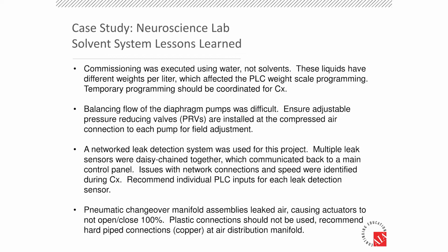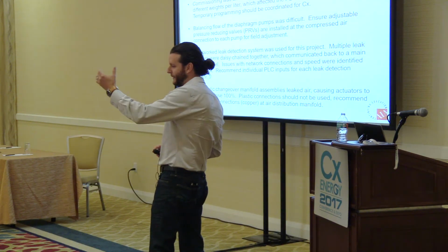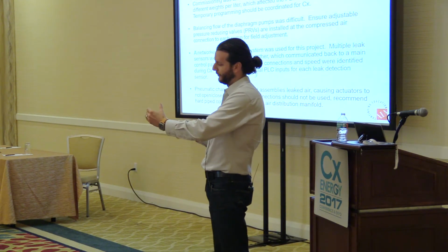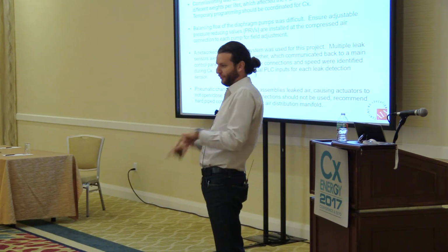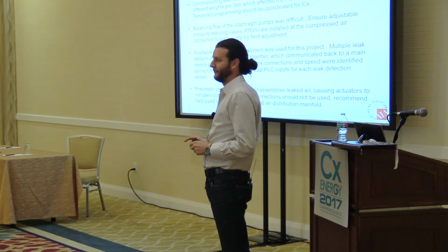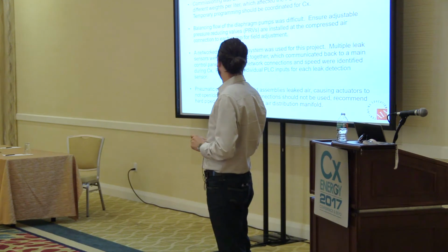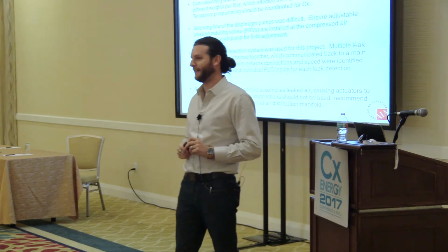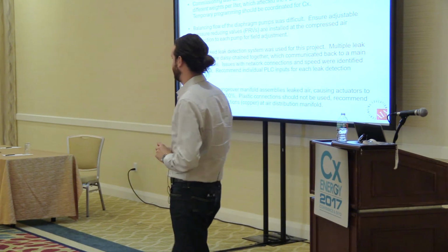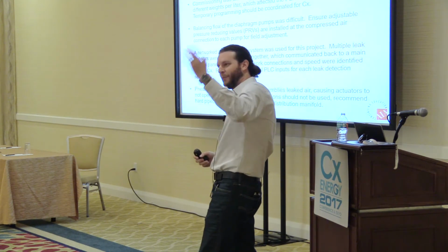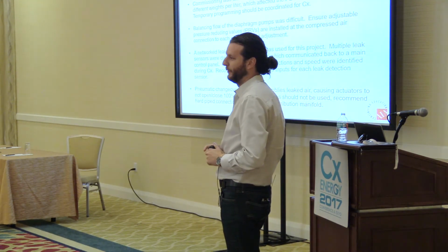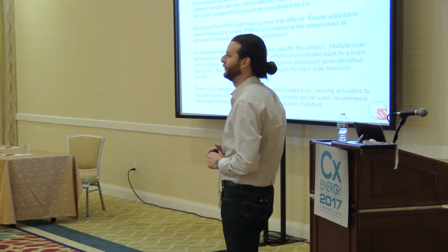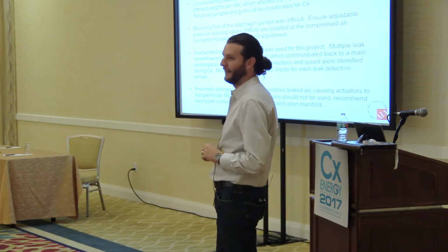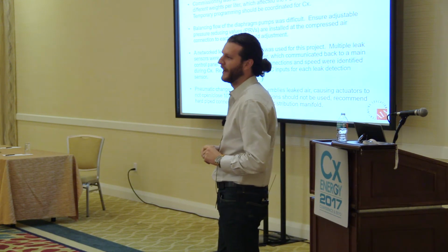And then secondly, if you're using pneumatic systems, this one we had an air compressor. Compressed air came into a manifolded system, and solenoid valves would then take that and shoot air out to the different pneumatic valves for control. This one had polytube connections at the manifold, and it was wreaking havoc. They were coming loose, and the valves weren't opening and closing properly. So if you're going to use pneumatic systems for mission critical applications, use copper. Do it right. Hard connections.